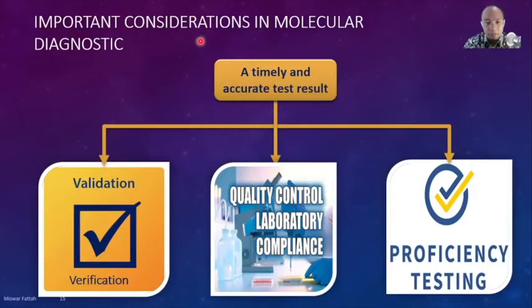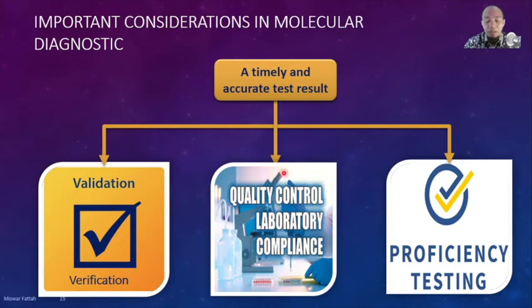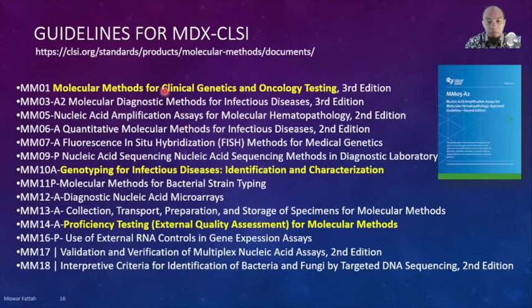Important considerations in molecular testing include validation and verification before routine use, maintaining quality control during routine operation, and proficiency testing after running for some time. These three elements are very important to maintain quality in the molecular laboratory. Some guidelines are now available, especially from CLSI, which we can use to validate.